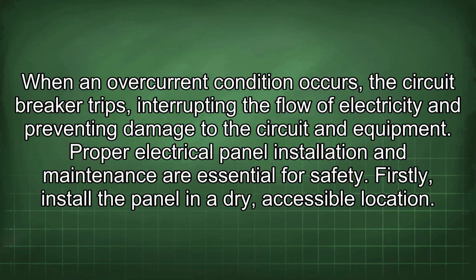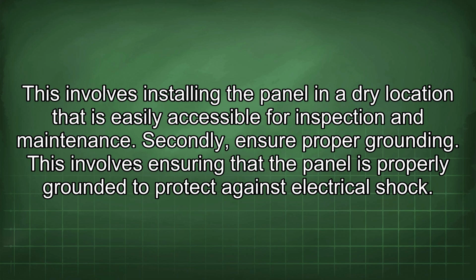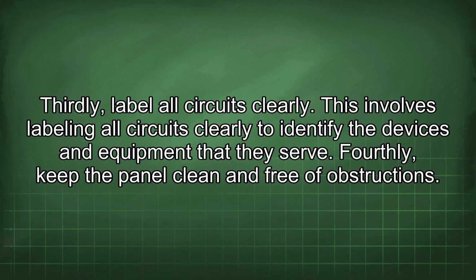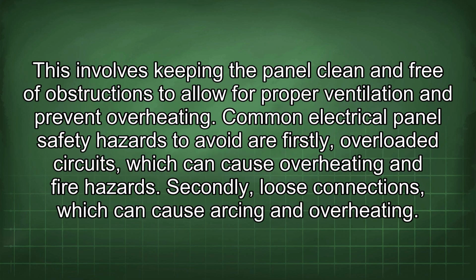Firstly, install the panel in a dry, accessible location. This involves installing the panel in a dry location that is easily accessible for inspection and maintenance. Secondly, ensure proper grounding. This involves ensuring that the panel is properly grounded to protect against electrical shock. Thirdly, label all circuits clearly. This involves labeling all circuits clearly to identify the devices and equipment that they serve. Fourthly, keep the panel clean and free of obstructions. This involves keeping the panel clean and free of obstructions to allow for proper ventilation and prevent overheating.